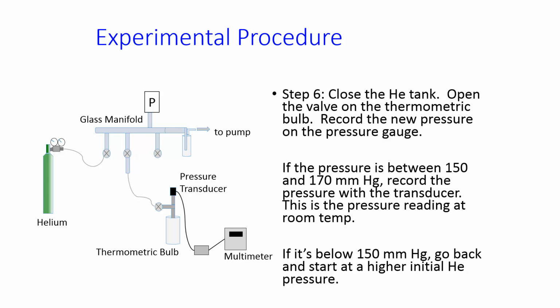As the helium expands into the thermometric bulb, the pressure read on the pressure gauge is going to decrease because now that helium that was in the manifold is now spread out through the manifold and the bulb. So the pressure will go down, and it should go down to about 150 to 170 millimeters of mercury. If it's much higher or much lower than that, pump everything out and start over.